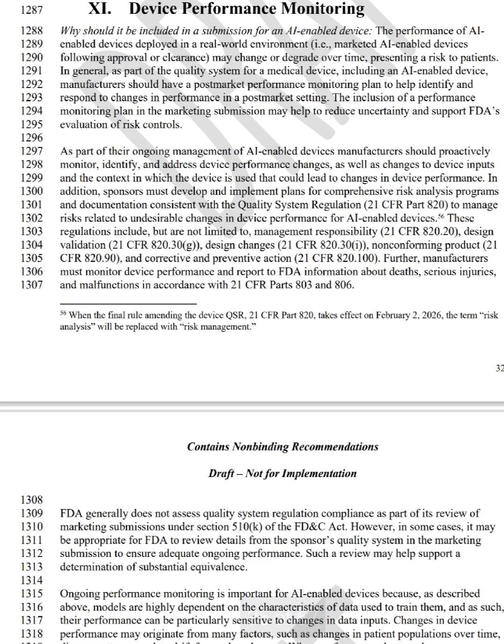Device performance monitoring. Once an AI-enabled device is on the market, ongoing monitoring is crucial to ensure it remains safe and effective over time. The FDA highlights the importance of post-market surveillance for these devices. 1. Tracking performance. Manufacturers must monitor the device for potential issues, such as data drift. AI can perform worse over time as it encounters new unexpected data. Bias emergence. New data might introduce biases that weren't present during initial testing.